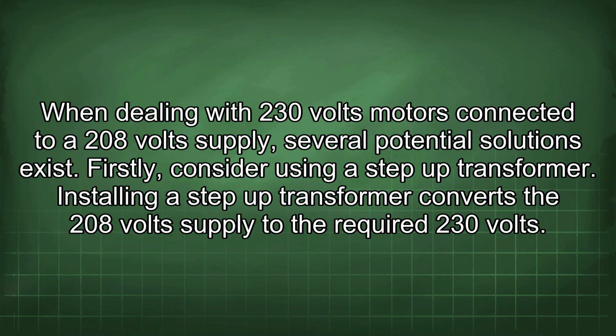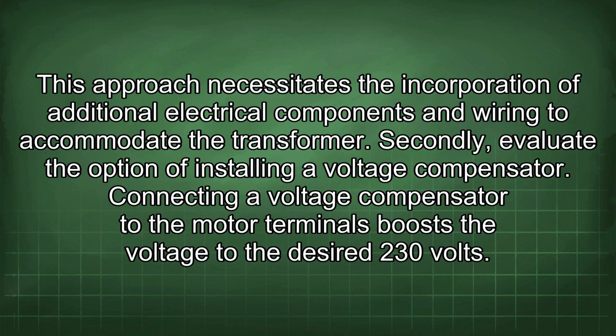When dealing with 230 volts motors connected to a 208 volt supply, several potential solutions exist. Firstly, consider using a step-up transformer. Installing a step-up transformer converts the 208 volt supply to the required 230 volts. This approach necessitates the incorporation of additional electrical components and wiring to accommodate the transformer.